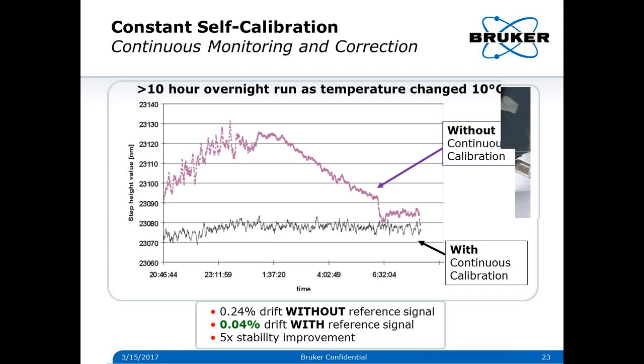Here's an example where we purposely changed the temperature in our testing lab by 10 degrees Celsius to get everything to thermally expand. The top chart shows the measurement without continuous calibration, and the bottom chart shows with continuous calibration — it compensated as the temperature and everything was thermally expanding. Using a zero-CTE standard, we got about a 5x stability improvement in this test. Our Contour Elite product also has additional external lighting which makes it easier to see low-contrast surfaces, plus a color camera option that can be overlaid on top of the Z-height 3D measurement, and newer display algorithms to help present the captured data.